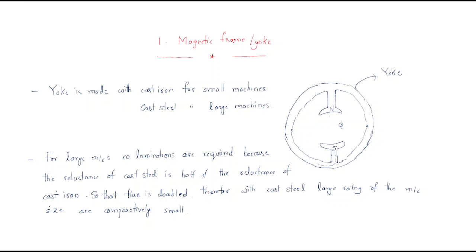The first part is the magnetic frame or yoke. The yoke is made with cast iron or cast steel. Cast iron is used for small machines, and cast steel is used for large machines. Cast steel has less reluctance for magnetic flux, whereas cast iron has more reluctance compared to steel.